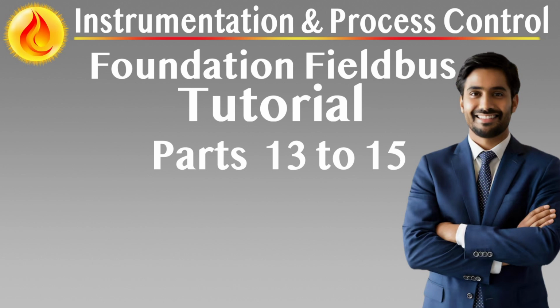Integration with host systems requires early coordination between the control, instrumentation, and IT teams. Host systems must support Foundation Fieldbus standards natively, including system management, device diagnostics, function block configuration, and DD/CFF interpretation. The planning phase must confirm compatibility of host DCS hardware, Fieldbus interface modules, FIMs, and asset management platforms with the selected device models and firmware revisions.